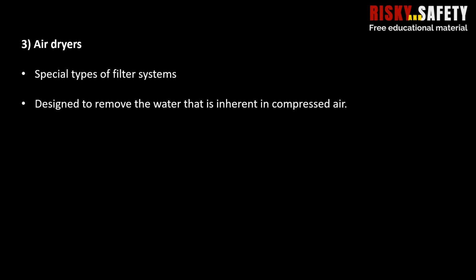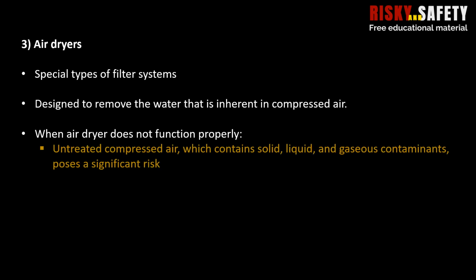Air dryers. Special types of filter systems that are specifically designed to remove the water that is inherent in compressed air. When an air dryer does not function properly, the untreated compressed air, which contains solid, liquid and gaseous contaminants, can pose a significant risk as it can damage your air system and end product.